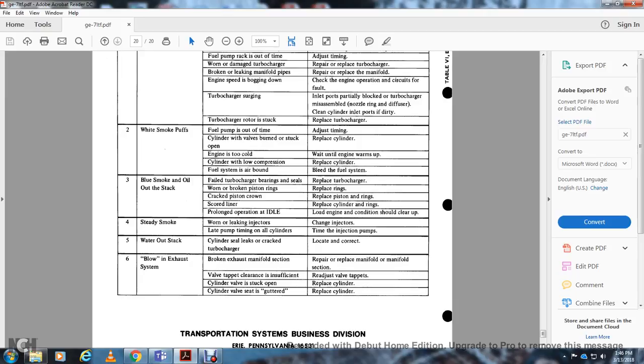Water out of the stack. Cylinder seal leaks or cracked turbocharger: locate the crack and correct. Blow in exhaust system, broken exhaust manifold: repair or replace manifold section. Valve tappet clearance insufficient: readjust valve tappets. Cylinder valve stuck open: clean, or replace cylinder. Clean valve seat, or replace cylinder.